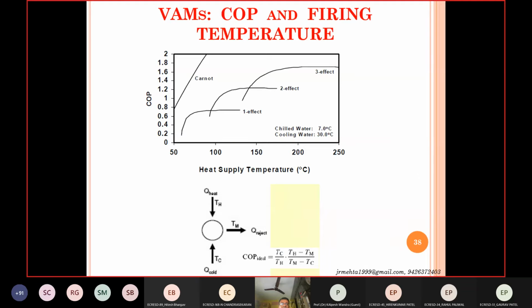So with the vapor absorption machines, if you go for single effect, you need lower temperatures from your solar collector, but then the COP will also be low, right? Heat supply temperature as it is shown here. So if you are utilizing more economical solar collectors, which cannot provide very high temperatures, then you have to be satisfied with the lower COPs provided by the single effect, right? If you are going for more costly concentrating collectors, then you may go for a double effect, which can deliver higher COPs. And the next stage is triple effect.